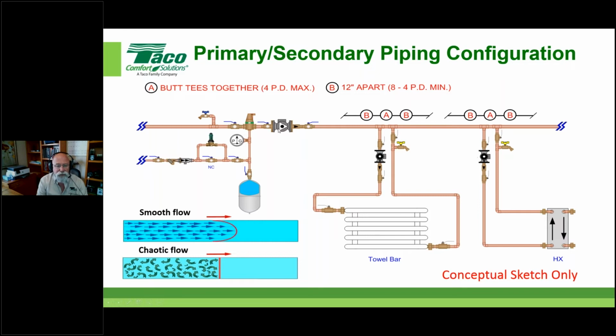But notice this, if I come out of this circulator downstream right after here, I'm going to be in a chaotic flow pattern because of what the circulator did by adding that mechanical energy to the fluid, right? It's going every which way. But once it goes out on this straight piece of pipe for a certain amount of distance, then it goes from this chaotic flow back to a nice smooth flow pattern before it gets to this first tee. This is what we're talking about right here.